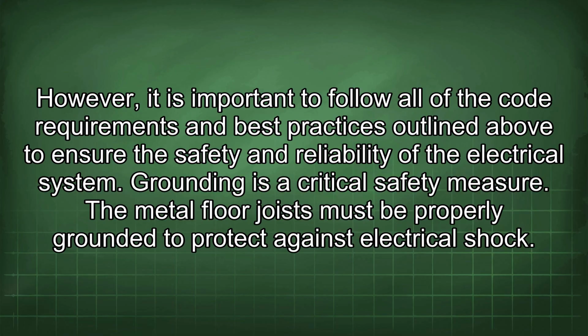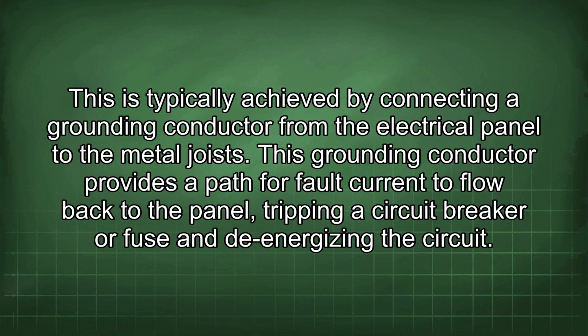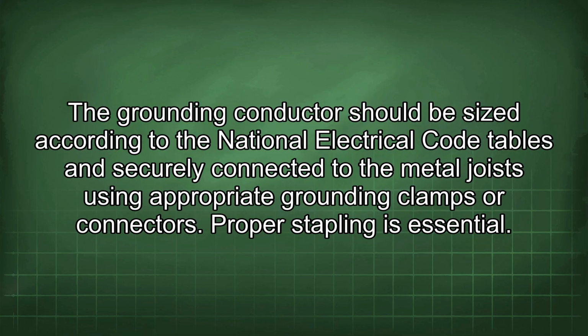Grounding is a critical safety measure. The metal floor joist must be properly grounded to protect against electrical shock. This is typically achieved by connecting a grounding conductor from the electrical panel to the metal joists. This grounding conductor provides a path for fault current to flow back to the panel, tripping a circuit breaker or fuse and de-energizing the circuit. The grounding conductor should be sized according to the National Electrical Code tables and securely connected to the metal joists using appropriate grounding clamps or connectors.